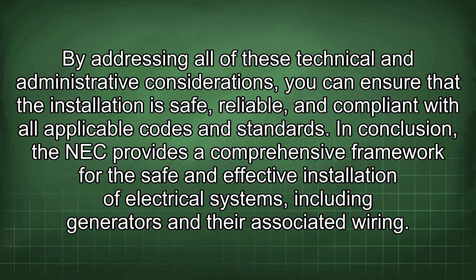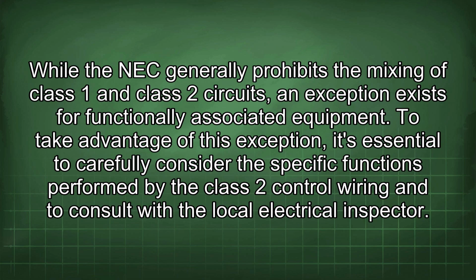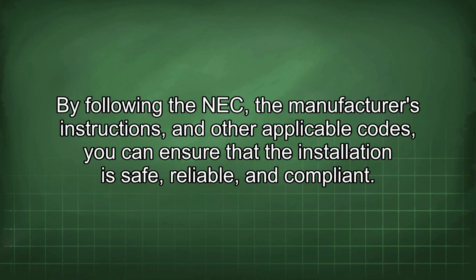In conclusion, the NEC provides a comprehensive framework for the safe and effective installation of electrical systems, including generators and their associated wiring. While the NEC generally prohibits the mixing of Class 1 and Class 2 circuits, an exception exists for functionally associated equipment. To take advantage of this exception, it's essential to carefully consider the specific functions performed by the Class 2 control wiring and to consult with the local electrical inspector. By following the NEC, the manufacturer's instructions, and other applicable codes, you can ensure that the installation is safe, reliable, and compliant.